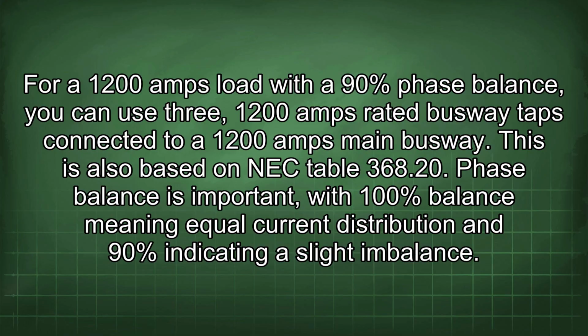For a 1200 amps load with a 90% phase balance, you can use 3 1200 amps rated busway taps connected to a 1200 amps main busway. This is also based on NEC Table 368.20. Phase balance is important, with 100% balance meaning equal current distribution and 90% indicating a slight imbalance.